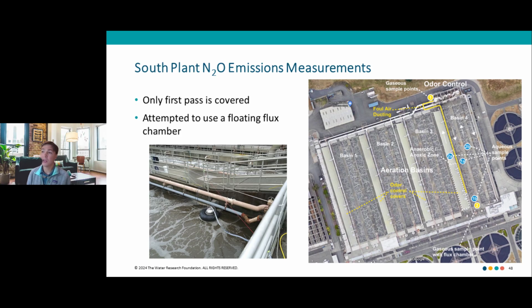We did a baselining in 2021 where we were operating in our non-nitrifying conventional activated sludge configuration. During that time, we had aqueous probes in the second pass of our aeration basin. We were limited in the cable length we had for those, so I would have preferred to locate them differently, but that's where we located them. We measured the nitrous oxide emissions at the odor control like we did at Brightwater. And then we had a floating flux chamber, which you can see there on the left, and tied that into our gaseous measurement analyzer for some of that baselining.